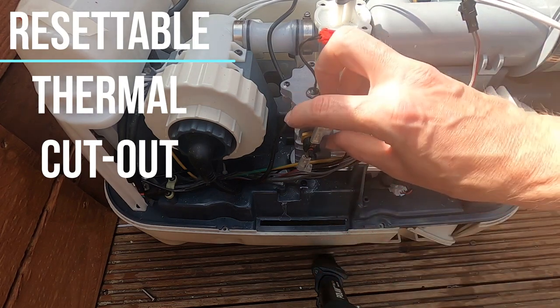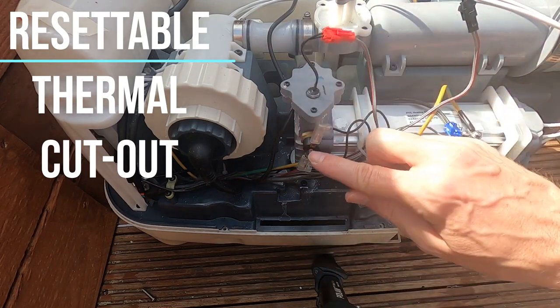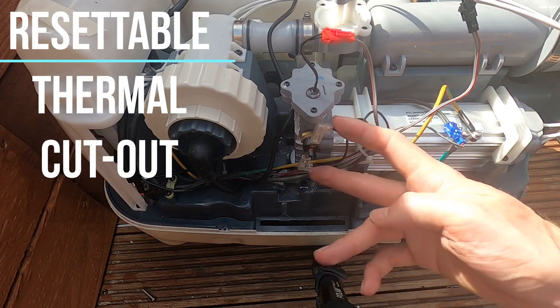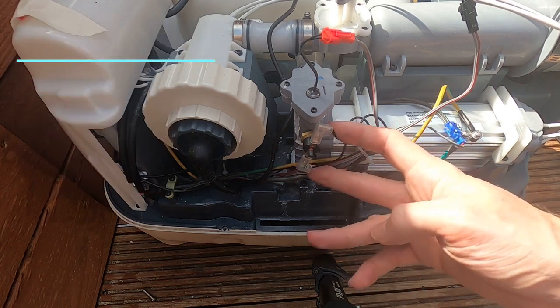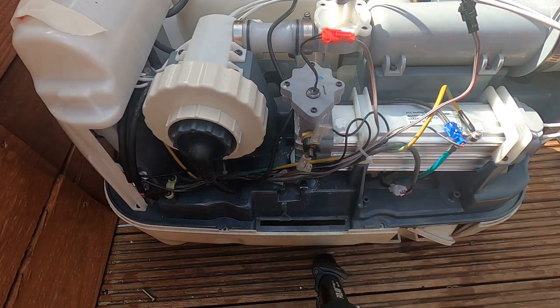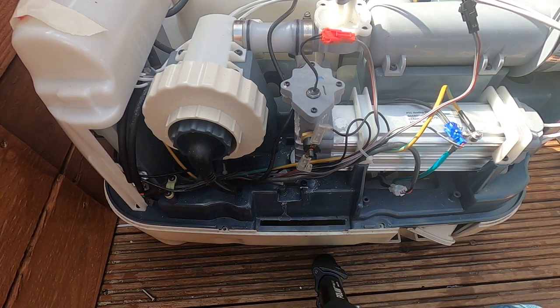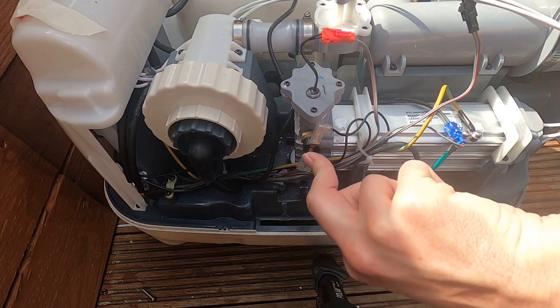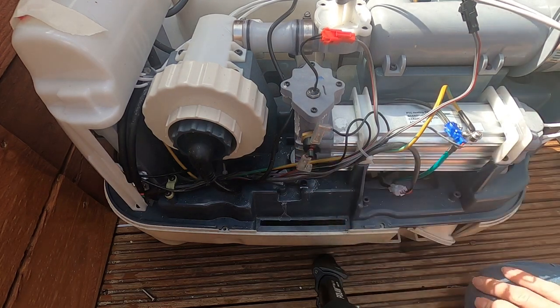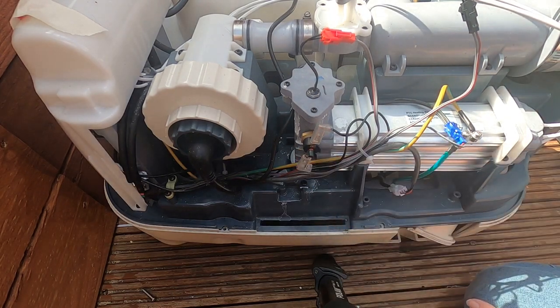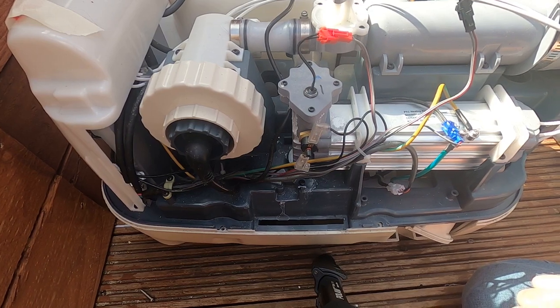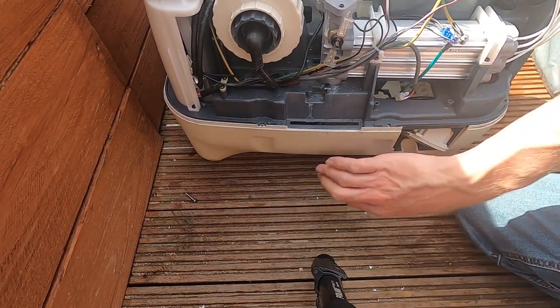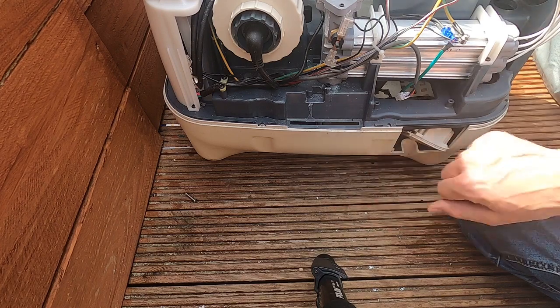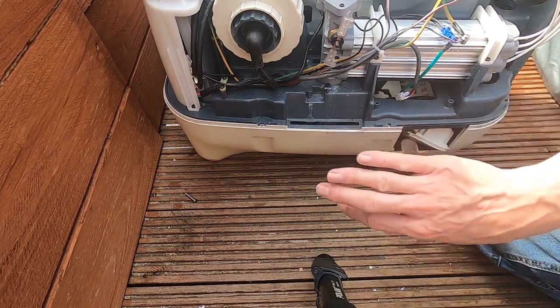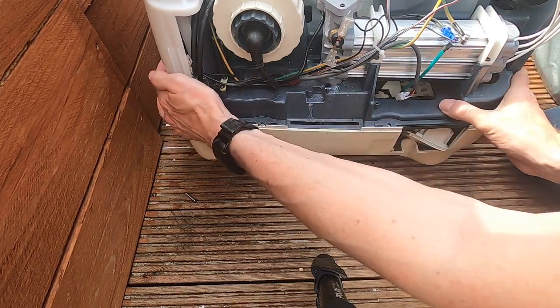So if this gets too hot, that will pop out and it will tell the controller to stop running the heaters. So again, you'll get water flow, everything will look like it's working, but the heater won't heat up. So sometimes you need to press that quite hard if it's had a thermal cutout event. That's that component. Now the pump lives underneath, as does the power supply and the other components.